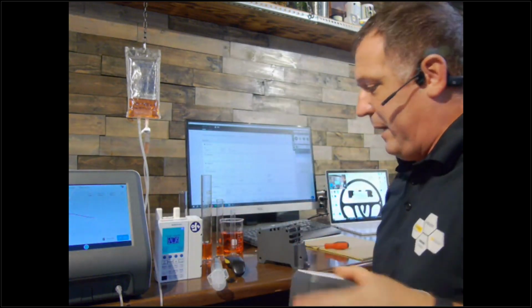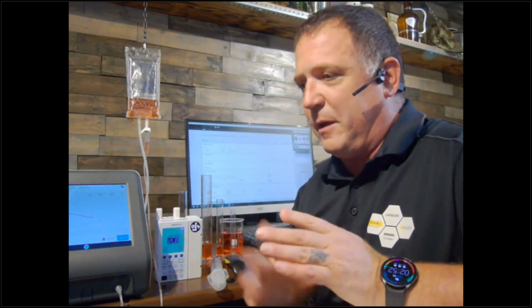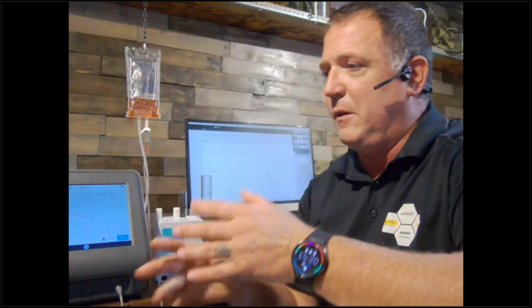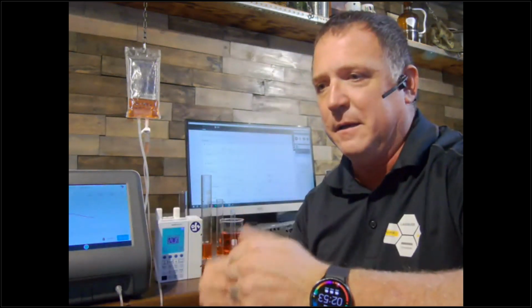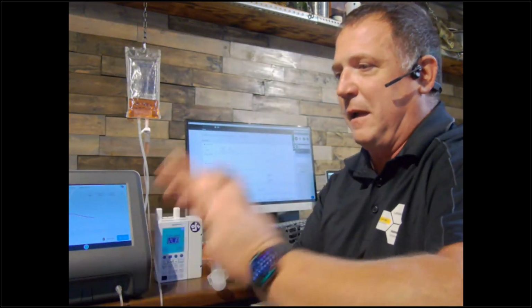So I can send this channel into Fluke to get calibrated while I continue using the rest of my IDA-6. A lot of customers do this: say they each have 3-channel IDA-6s, so they buy a few extra 4-channel and 2-channel units and keep spare channels on hand. They take two channels out, send them back for calibration, and keep using the rest. When those two channels come back, they put them into the next IDA-6, take out two more, and send those in. That way they're never down. So while calibration is once a year, it's designed so you're never out of service.